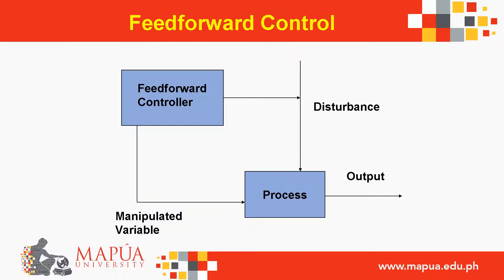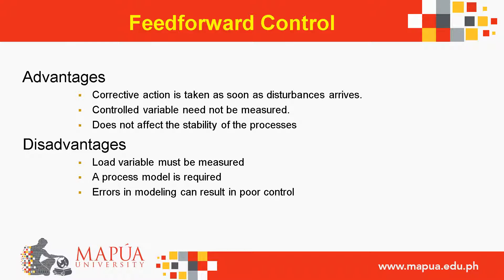Here is the block diagram for a feedforward control. Feedforward control advantages: corrective action is taken as soon as a disturbance arrives, the controlled variable need not be measured, and it does not affect the stability of the process. Disadvantages: the load variable must be measured, a process model is required, and errors in modeling can result in poor control.